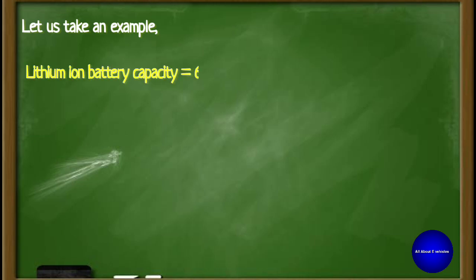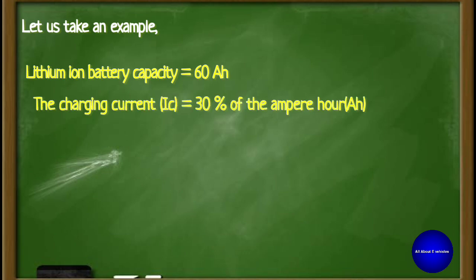Lithium-ion battery capacity of 60 ampere-hours. What will be the charging time and current required for this 60 ampere-hour battery? The charging current is 30% of ampere-hours, that is 18 amperes. This is the required charging current for this lithium-ion battery.